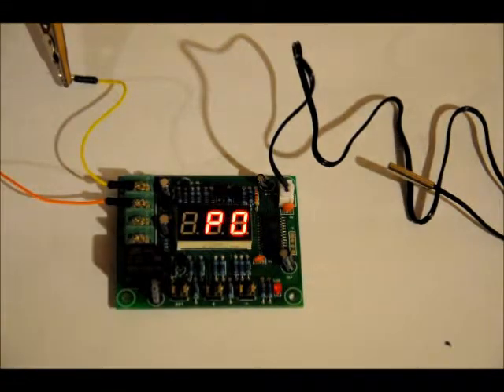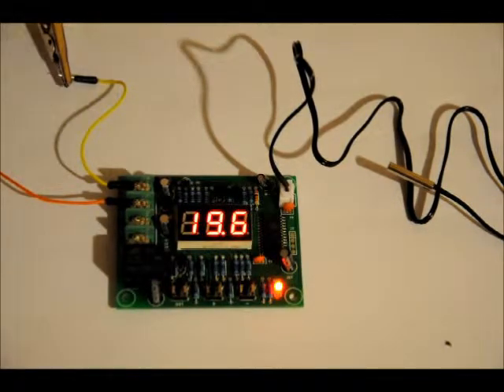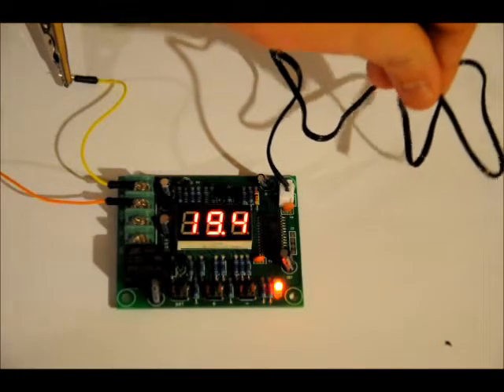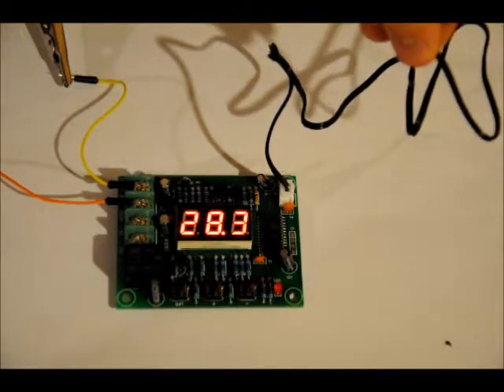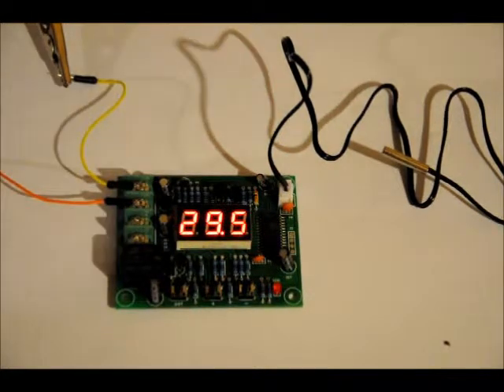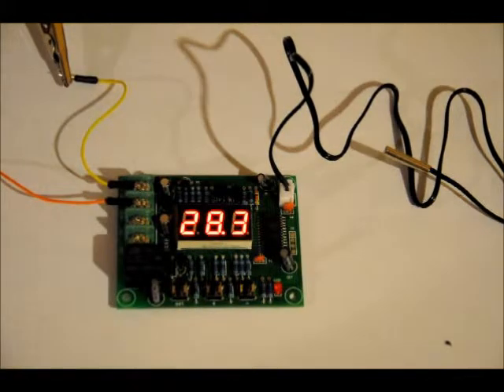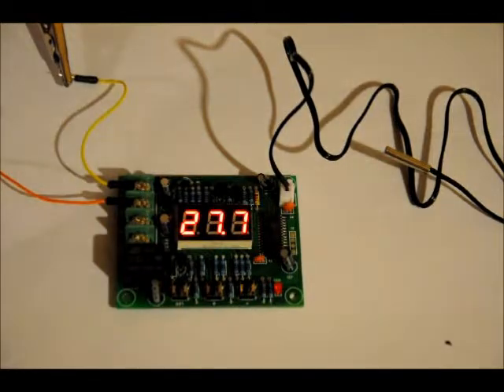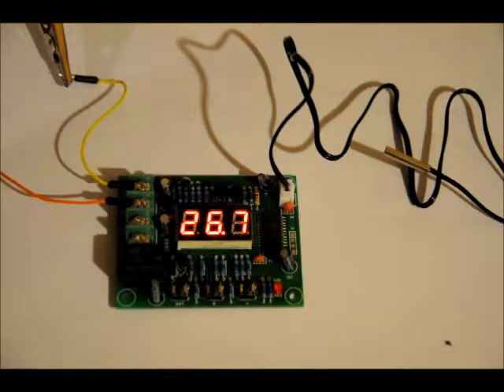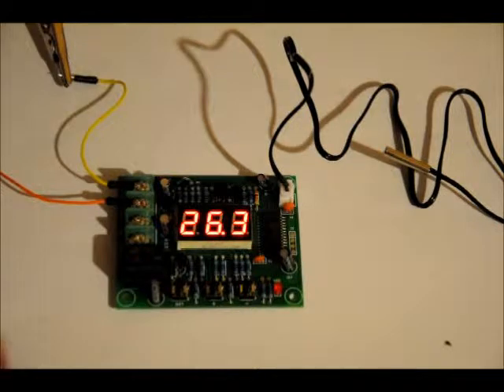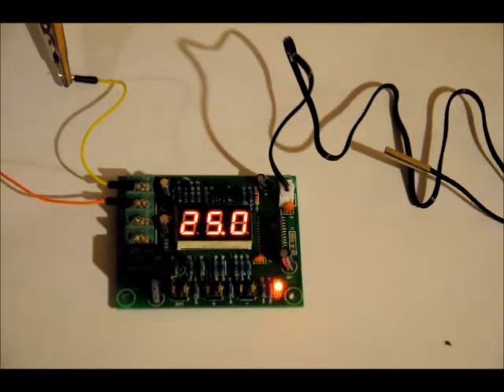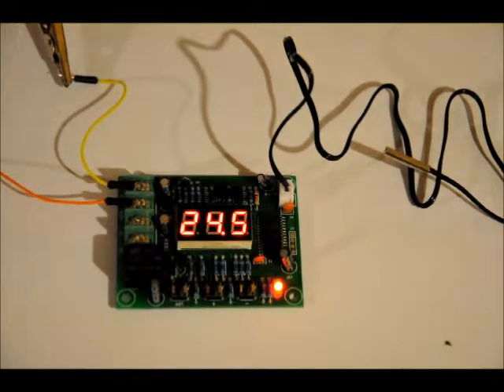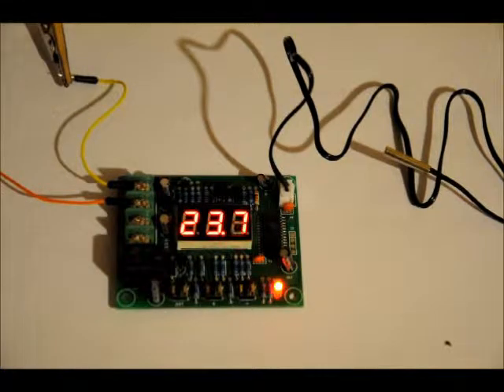So we've set hysteresis. The hysteresis is still a value of two. So the relay should turn on. There we go. And so what I'll do is I'll simulate warming it up again. And the relay will turn off at 27 degrees. That's our hysteresis. Now it will turn off when it goes back below 25 degrees. So it gets a bit complicated, but it's very accurate. Now again, you can change the reference temperature at any time. So it's very convenient. When that goes back below 25 degrees, we've set a reference temperature to 25 degrees. Our hysteresis is at 27 degrees. So once it goes past 27, the relay turns on. When it comes back down past 25 degrees, the relay turns on again. So in case you're turning on a fan. Cooling mode. Or sorry, heating mode. Anyway, so let me show you the other aspects of this neat little module.